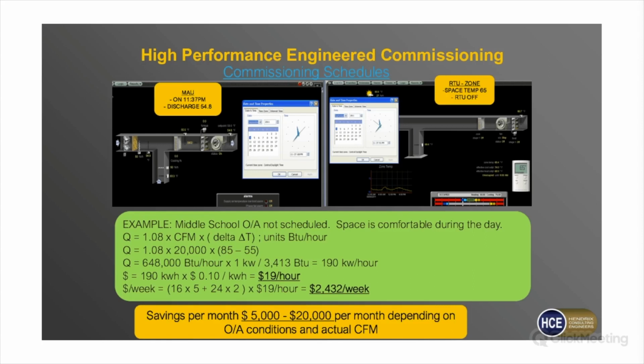One common thing that comes up when we're commissioning is checking the outside air machines. So here's a quick thing that we found on one job, where on the left, you'll see that the makeup air unit at 11:37 p.m. is discharging 54-degree air. Obviously, nobody's at school at 11:37. One of the RTUs that was getting fed by that space, its space temperature was 65, which is well below the cooling set point, especially in the after hours condition. And so we were able to identify that makeup air had been running and it was stuck. For some reason, it was locked on.